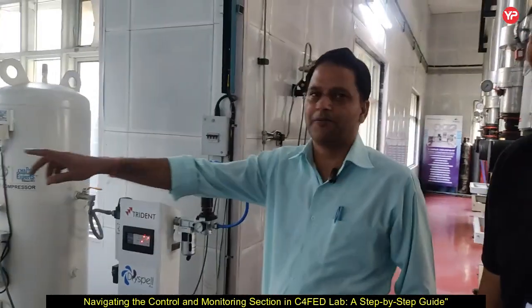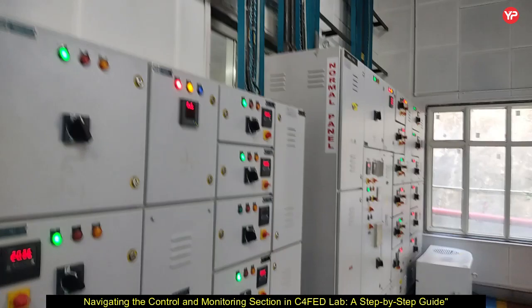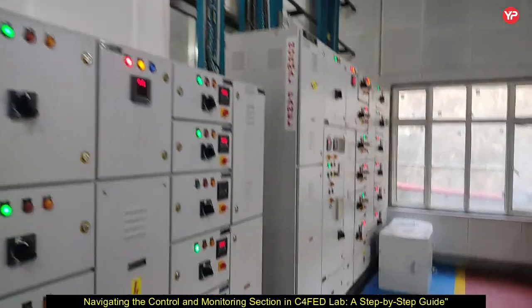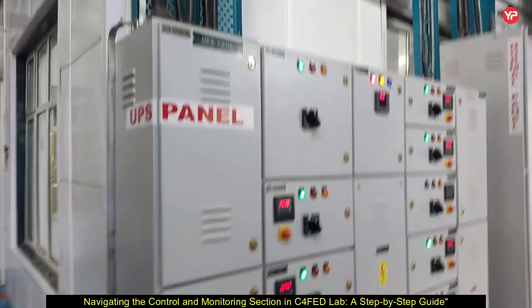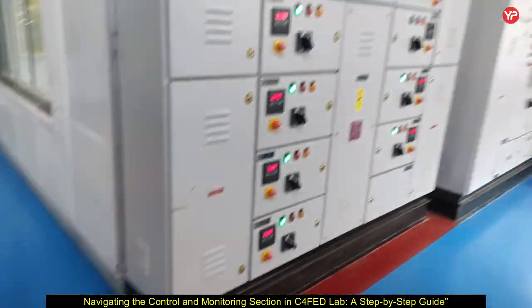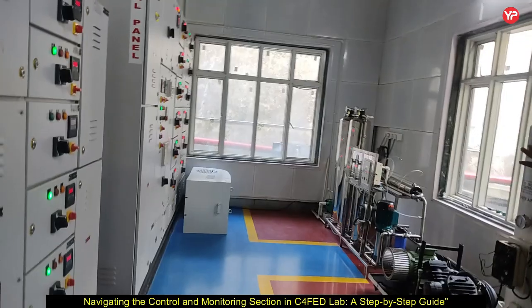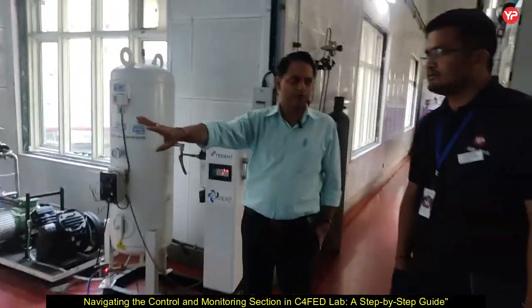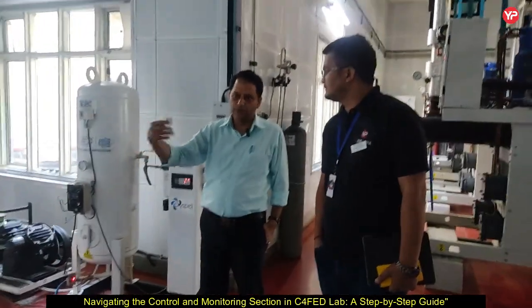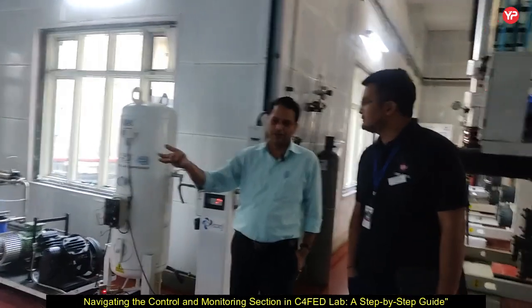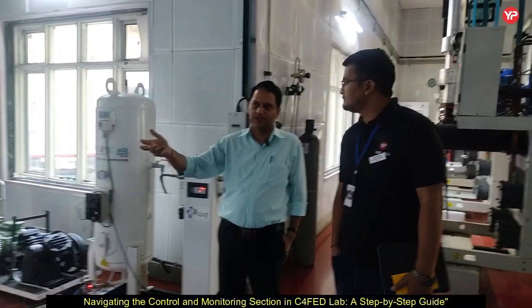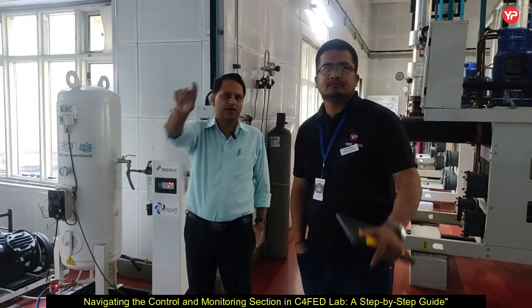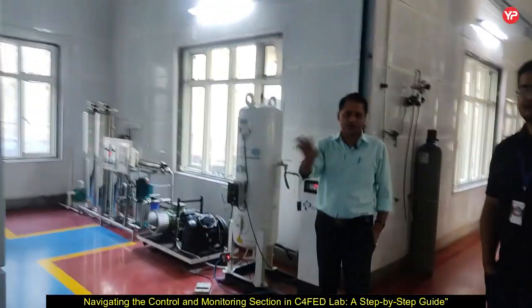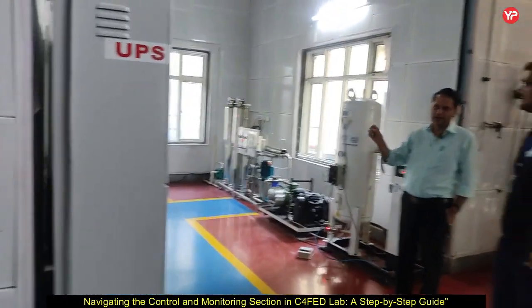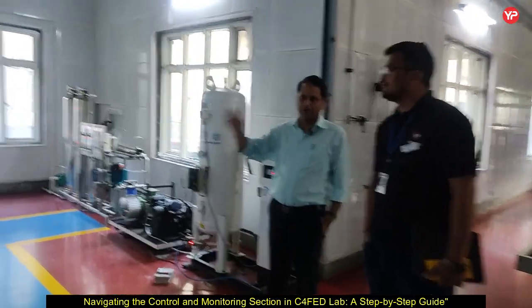So this is our power management system. If the normal power works fine, this panel will operate. But if due to some bad weather or accident there is a normal power failure, then it is shifted to this UPS. And if the UPS cannot be sustained for longer hours, 12 hours or something like that, then it is shifted to the DG. And this is automation. It is very quick, hardly a few seconds for the shift.